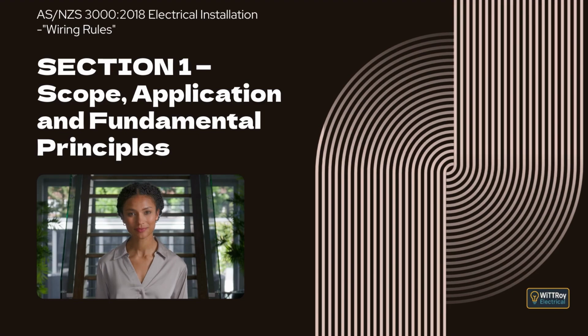The key idea is that unused conductors must never be left floating, because they can still become energized due to induction or other effects. Clause 1.5.11.5 Different circuits and installations. This clause explains that protection must be provided against harmful influence between different types of circuits or different installations.